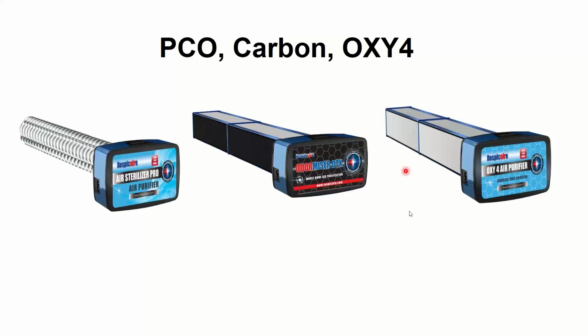There are some technologies out there that have UV lights in them that are not used for killing stuff on the coil. They're specifically used for killing stuff in the air. But they work very, very differently than what I just described. What I just described was the light of the bulb shining on something to kill those germs with the UV light being the killing factor, right? What I'm going to talk about now is using a UV light, but not using it as a killer. It's going to be used as a catalyst so something else can be the killer, right? It seems weird I'm having a presentation about killers, probably get arrested later.